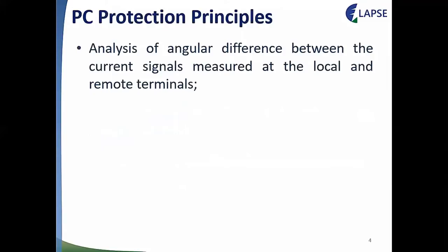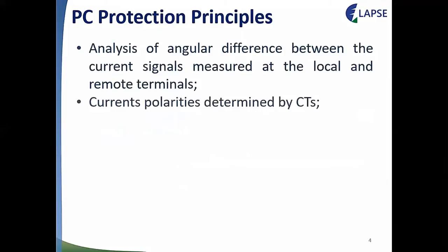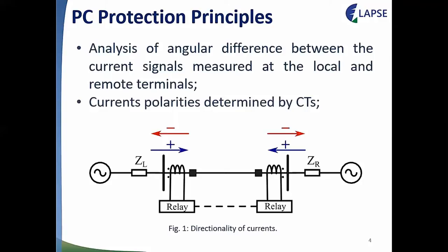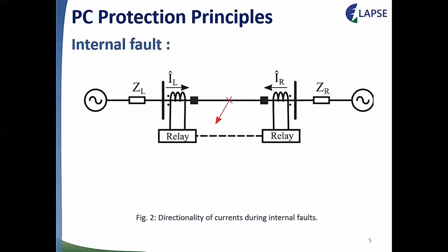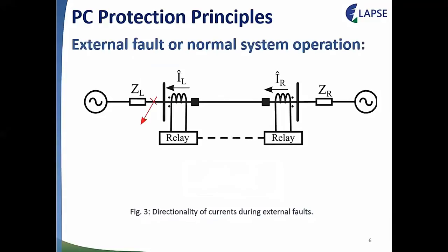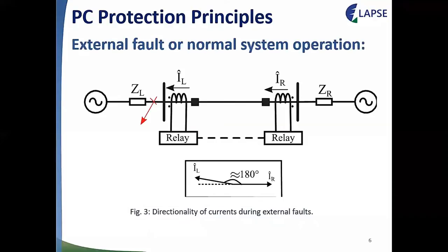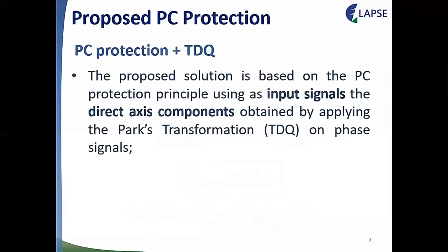The PC protection principles are based on analysis of angular differences between the current signals at the local and remote terminals of a given transmission line. Polarities are determined by the CTs (current transformers), so current entering the line is positive and current leaving the line is negative. For an internal fault, both local and remote currents are entering the line, so the angular difference is ideally zero, but in real cases almost zero due to the lag caused by capacitive effects. For an external fault or normal system operation, one current enters and the other leaves, so they are ideally in counter phase — approximately 180 degrees apart. These angular differences characterize internal versus external faults.